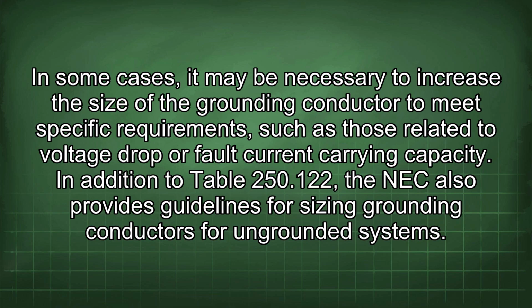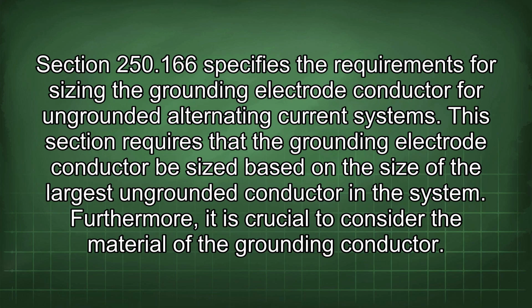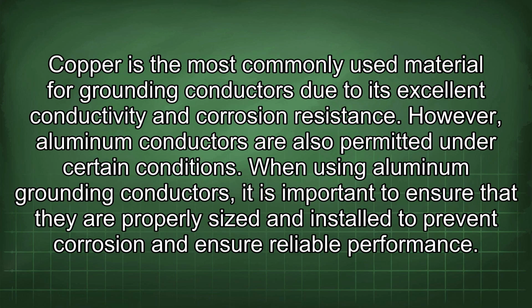In addition to Table 250.122, the NEC also provides guidelines for sizing grounding conductors for ungrounded systems. Section 250.166 specifies the requirements for sizing the grounding electrode conductor for ungrounded alternating current systems. This section requires that the grounding electrode conductor be sized based on the size of the largest ungrounded conductor in the system. Furthermore, it is crucial to consider the material of the grounding conductor. Copper is the most commonly used material for grounding conductors due to its excellent conductivity and corrosion resistance. However, aluminum conductors are also permitted under certain conditions.